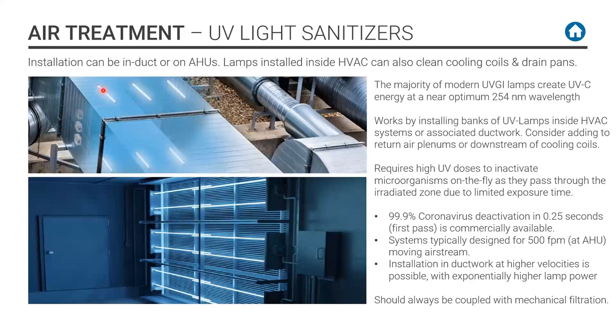In a standard, let's say 150 microwatt unit, you might need 6 to 10 seconds if you're running in the duct. The duct may be 1500 feet per minute. A coil is a much lower velocity, under 500 feet per minute. So again, it's something that you can consider. We're putting it in some buildings, but it has to be retrofitted. That's the UVC lights.